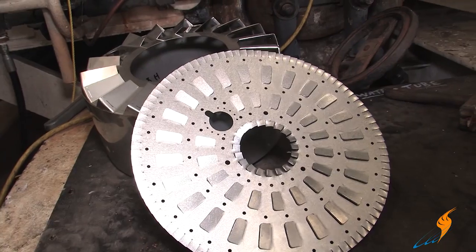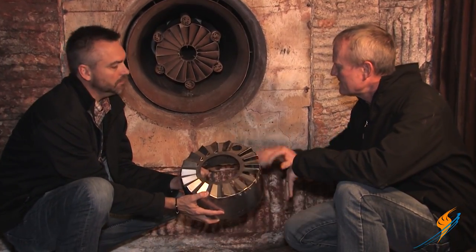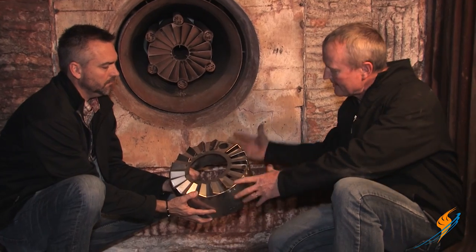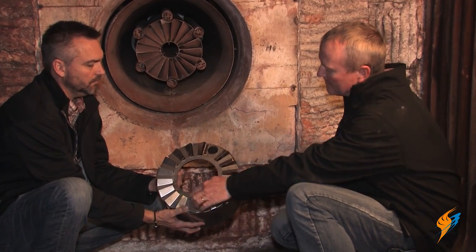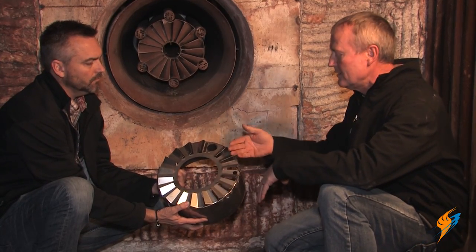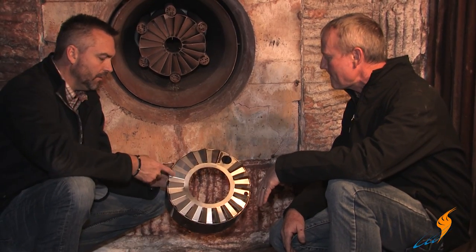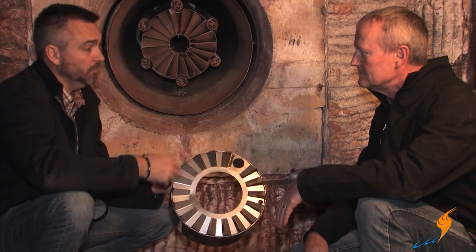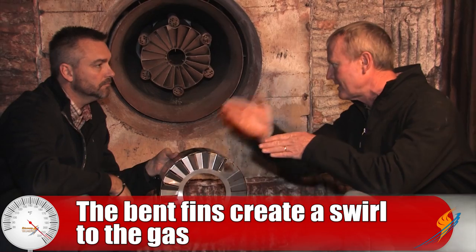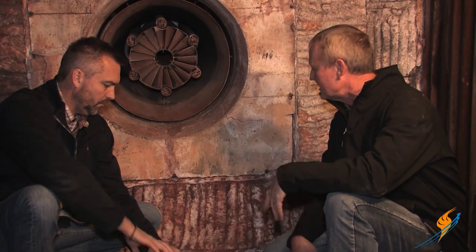Let's focus on the diffuser. We have a couple different diffusers here. This is pretty much the same style diffuser as what we have on the Todd burner — you've got your outside air and then inside air comes through here. Gas typically on this one will be here or they'll have spuds on the outside, but it's doing the same thing. You've got air coming through, cutting the gas, getting the mixture in that fashion. These are actually bent in a certain way so that when the air comes through, it spins — making that air spin when it cuts across that gas, we want that air spinning to get that mixture we're looking for, rolling it up to mix properly.